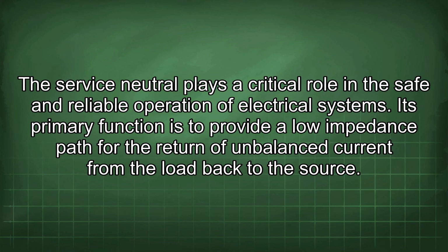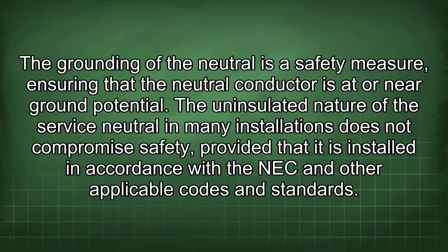Its primary function is to provide a low impedance path for the return of unbalanced current from the load back to the source. The grounding of the neutral is a safety measure, ensuring that the neutral conductor is at or near ground potential. The uninsulated nature of a service neutral in many installations does not compromise safety, provided that it is installed in accordance with the NEC and other applicable codes and standards.